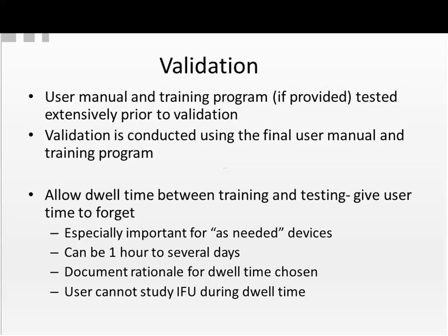Another very important point, the FDA concentrates on this. If you have a training program for users, you must allow a dwell time between training and testing. The purpose of this is to give the user time to forget what you taught him. It can be 1 hour, could be several days.